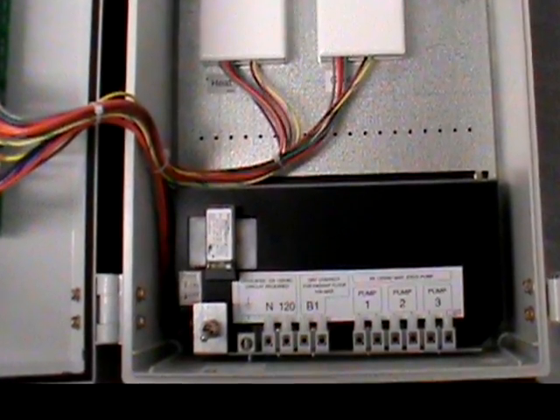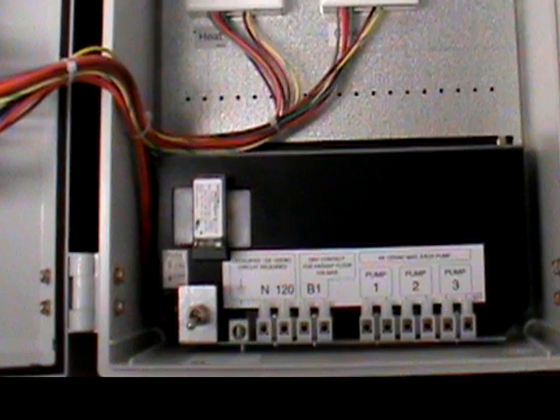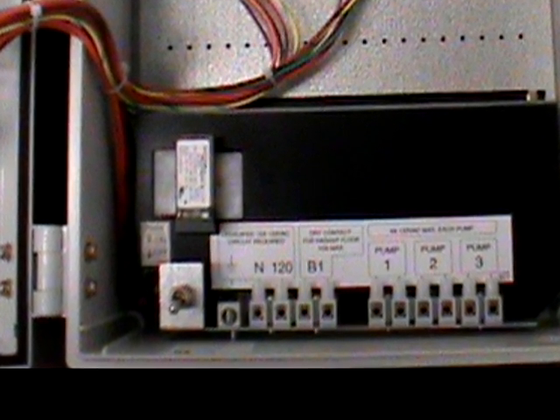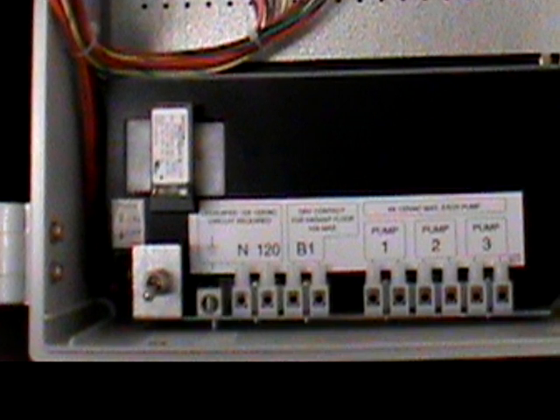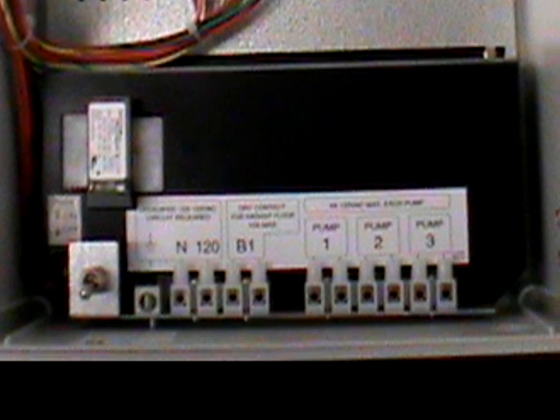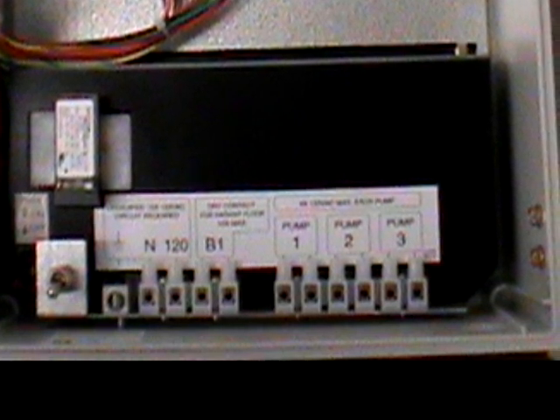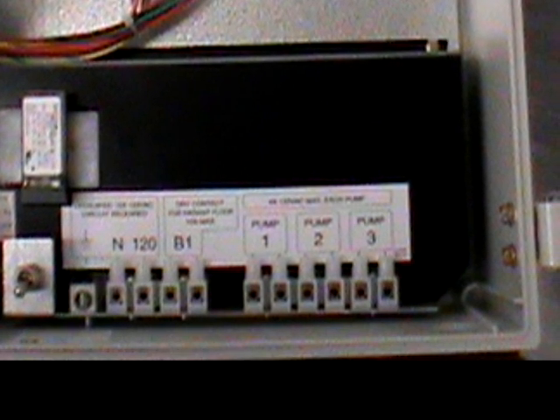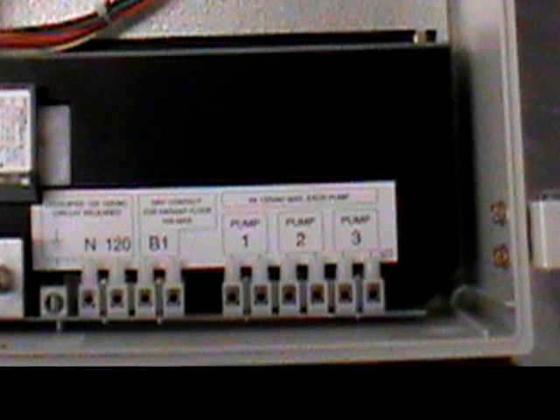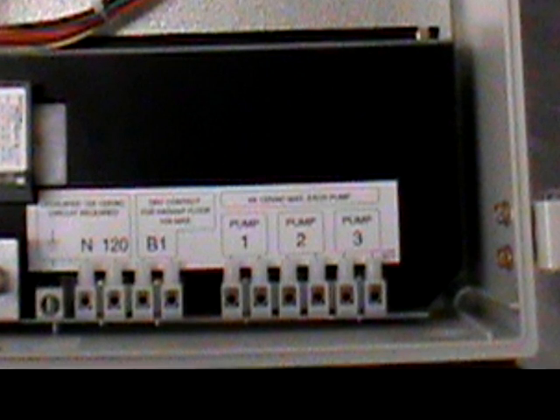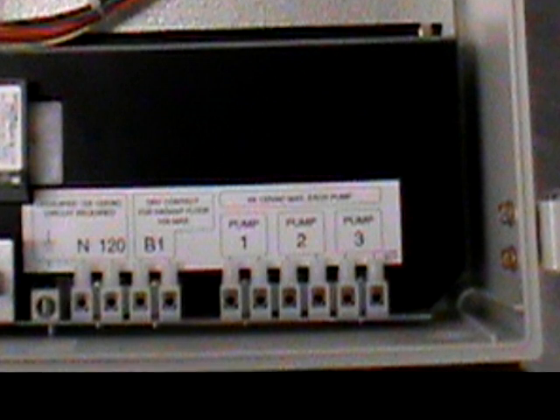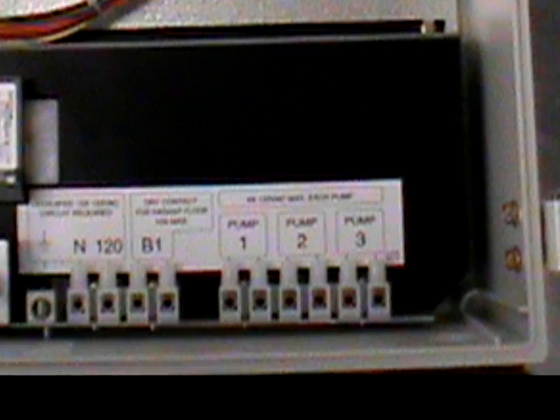Located on the lower right side of the cabinet are the high voltage connections. The main power switch and 120 volt input connection are located on the left. Next are the connections for the B1 dry contact as discussed earlier. Because this is a dry contact, either high or low voltage can be used depending on your individual needs. Again, this relay is only energized during the heating mode. Next are the 3 individual pump connections corresponding to each relay and zone from the circuit board. They provide 120 volts for circulator pumps to fan coils, A coils above furnaces, or radiant floor zones.